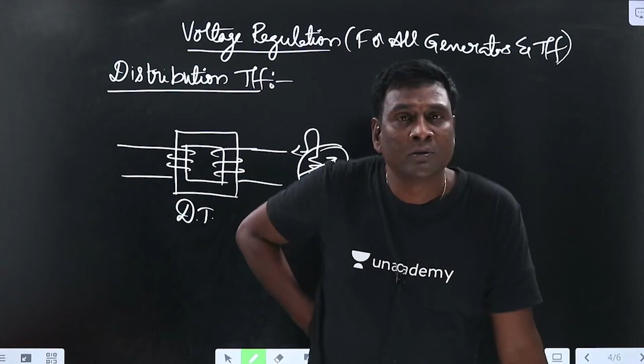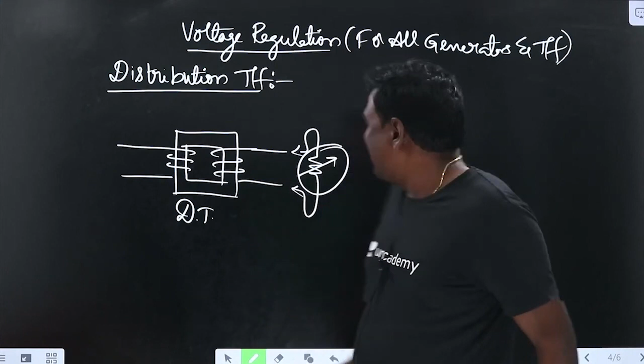In a distribution transformer, are you going to have taps? No, we are not going to have taps. At least on-load tap changers will not be there, because for a power transformer, an operating engineer will be there. A power transformer is a very big transformer, meaning a bulk of power is going to be transformed. So the moment it is a bulk of power, one operating engineer will be there. That operating engineer will maintain the taps.